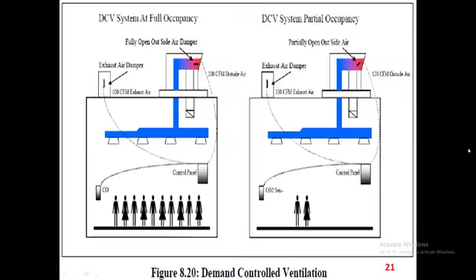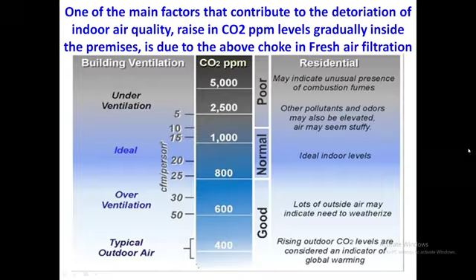And where do our buildings stand? I don't say in the college, because the college is all well ventilated. But if we take a case of IT buildings or any closed buildings, CO2 measurement, CO2 monitoring and CO2 control matter, against over ventilation or under ventilation. We need to see that you have ideal ventilation, and in 7 out of 10 cases it is only under ventilation. People are suffering from medical problems due to under ventilation. So it needs to be ideal or slightly over ventilated, to have CO2 ppm measured values around 900 to 1000, 900 to be precise.